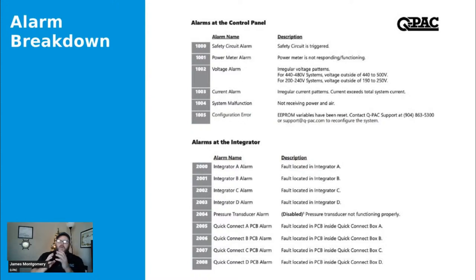Most, if not all, of our components have a manufacturer rating that says it's safe to operate within 5% of rated voltage. You start going outside of that and they cannot be responsible or uphold any warranties for keeping that device safe and keeping it from malfunctioning. So voltage alarm, that's that one. It's coming through the power meter.